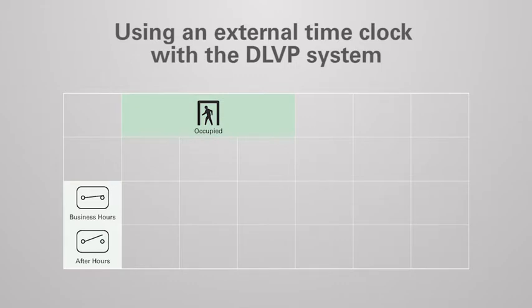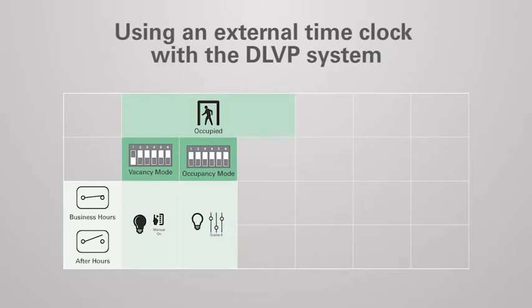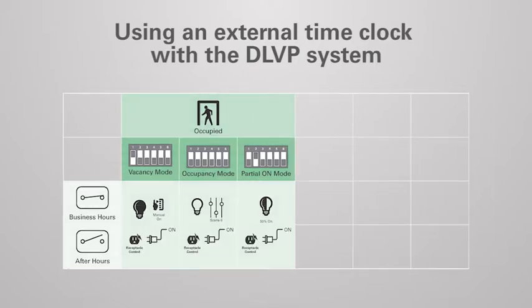When a space is first occupied, the behavior of the system is the same for both during business hours and after hours modes. If the power module is configured for vacancy mode, the occupant must use a wall station to manually turn lighting on. If configured for occupancy mode, lighting will turn on automatically to user programmable scene number six. If configured for partial on mode, lighting will turn on automatically to a 50% light level. In all configured modes, controlled receptacles will turn on.